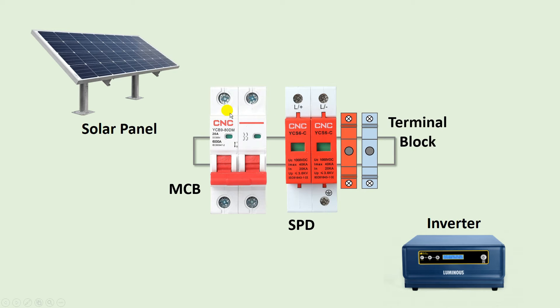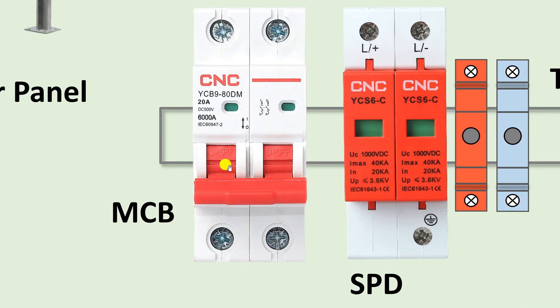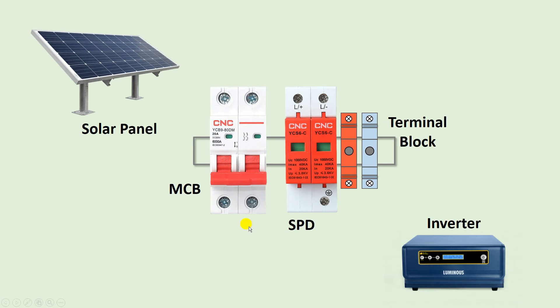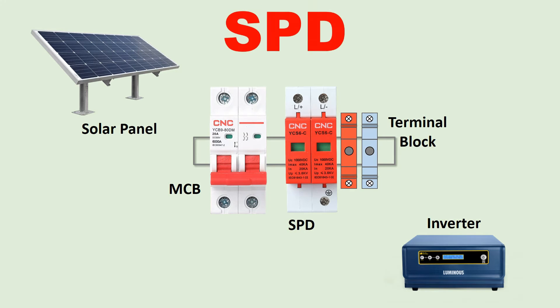Inside this DB box, the MCB you will use must be one that works on DC power supply. Here you can see 'DC 500 volt' is written — it means we can use this MCB up to 500 volts. The current rating of this MCB is 20 ampere.